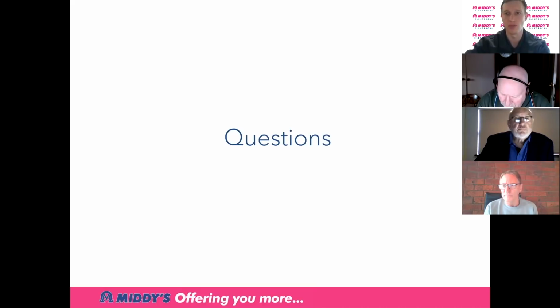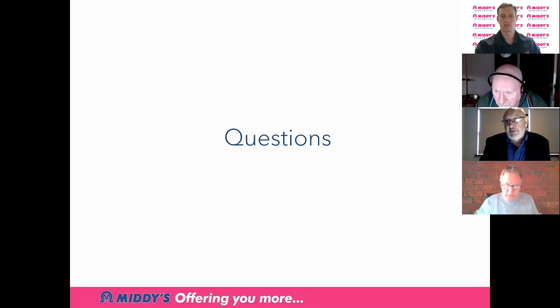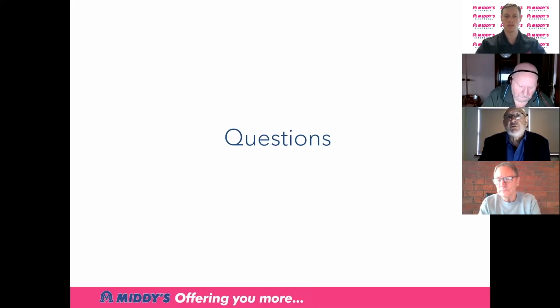So this one came through the chat as well, which I'll try and get to next. The chat's in a separate window. So, the type of RCD on community lights. Yeah, I saw that one, Jess. Yeah, that was about the community lighting. Community lighting fits non-residential. If you've got community lighting in a park or a walkway, you wouldn't actually want it on an RCD, to be quite honest, because you don't want it to trip and then have no light in that public access area or community park. So you could apply an exception, and that's why it comes under non-residential.